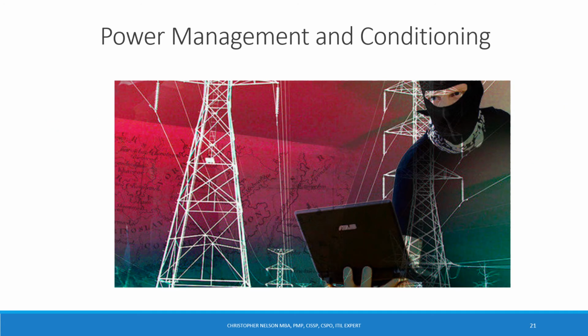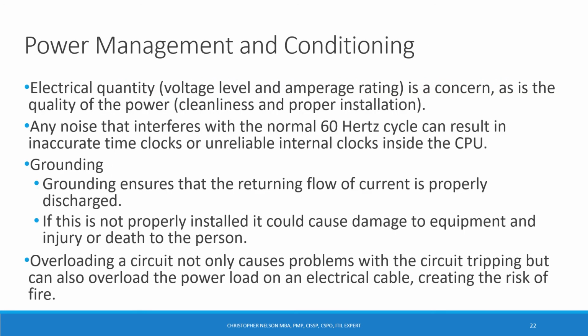When speaking about power management and conditioning, it's important to understand that electrical quantity is a concern, as is the quality of the power. Any noise that interferes with a normal 60 Hz cycle can result in inaccurate time clocks or unreliable internal clocks inside the CPU. Grounding and overloading are also important areas. Overloading a circuit not only causes problems with the circuit tripping, but can also overload the power load on an electrical cable, creating the risk of fire.